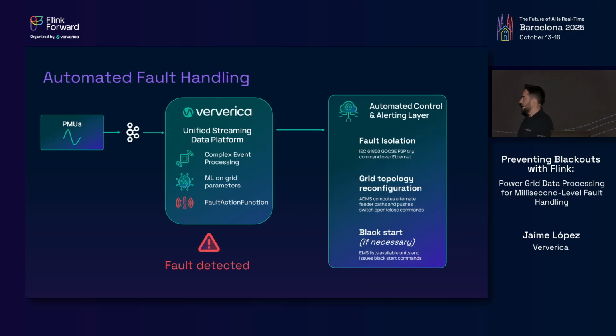Which also allows us to go a little bit beyond. So we detected the fault, we handled it by actioning some predefined mitigation mechanisms, but you can also prevent it from spreading. Luckily, in the electrical world, everything is really, really well procedurized and codified. So all the PMUs use the same protocols, all the SCADAs use the same protocols, all the breakers and trippers use the same protocols, and it's fairly easy for them to communicate with each other. In some cases, for example, via Ethernet. You can issue a trip command to a breaker of a plant over Ethernet.